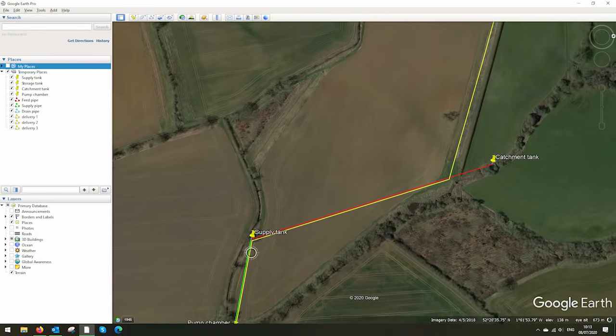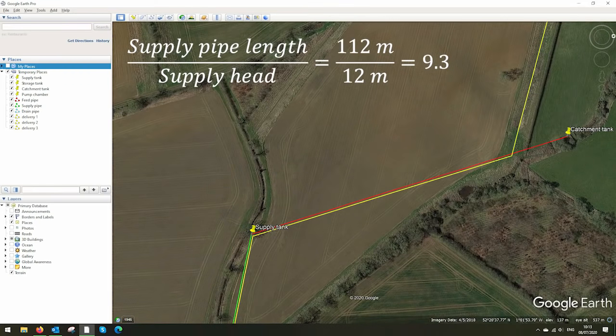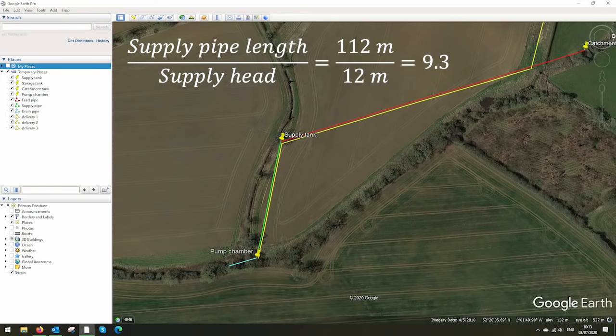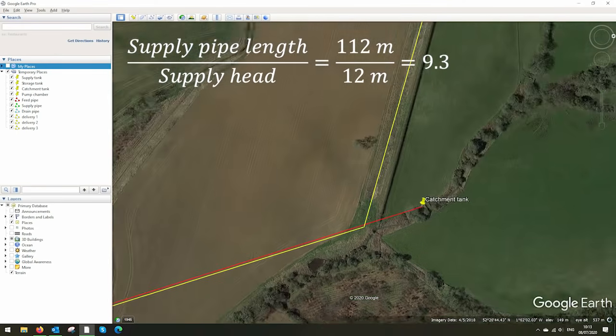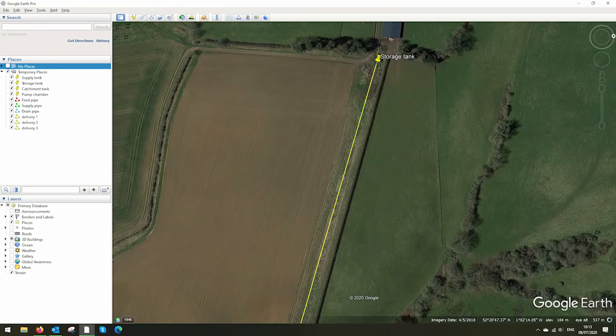Now you want to mark down all your pipe lengths and check your gradients. We've now got a head of 12 meters over a 112 meter stretch, giving a gradient of about 1 in 9, which is okay. We can calculate our delivery head as well to be 34 meters.